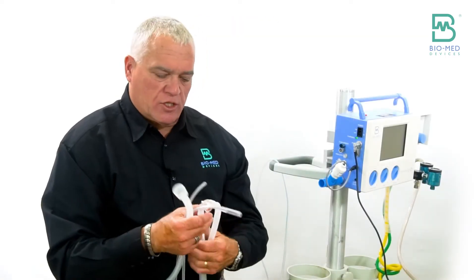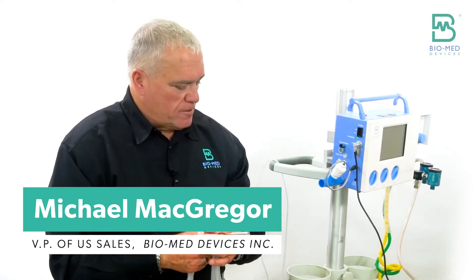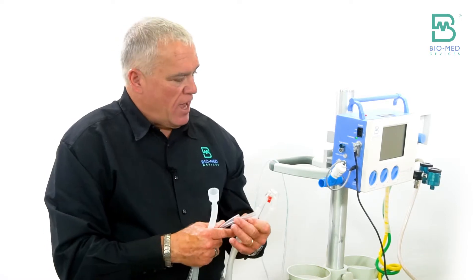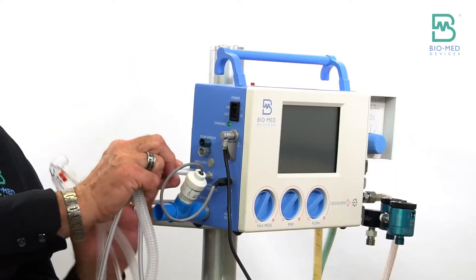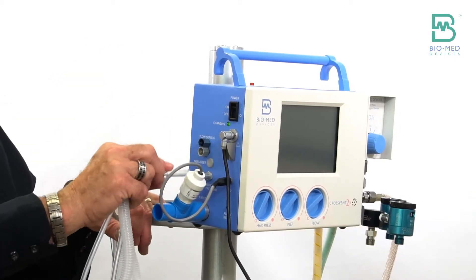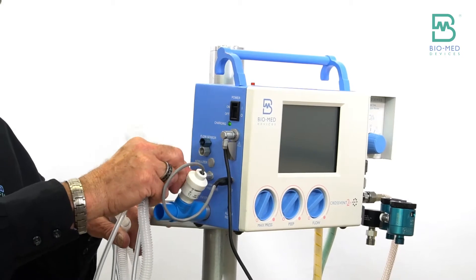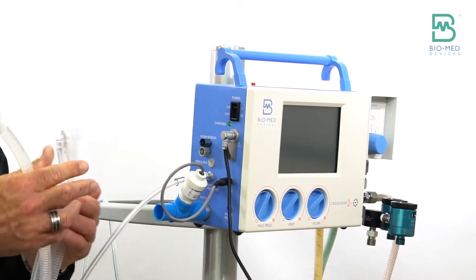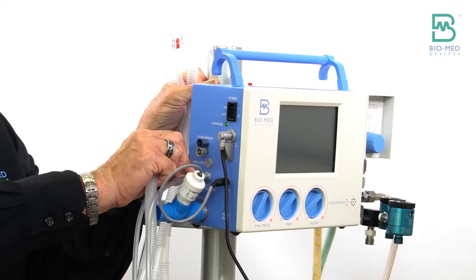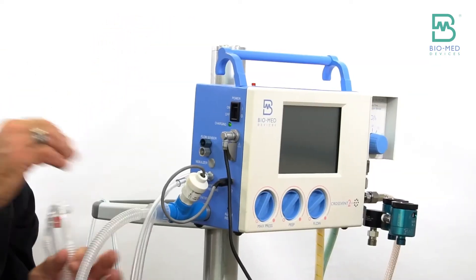I'd like to talk about the circuit connections on the CrossVent 2i Plus. The standalone version actually has a different size fitting for the pressure line here. It's a bigger fitting and the exhalation valve won't fit — that's just to keep them separate and make sure everybody connects them correctly. And then it has a 22 millimeter connection here.